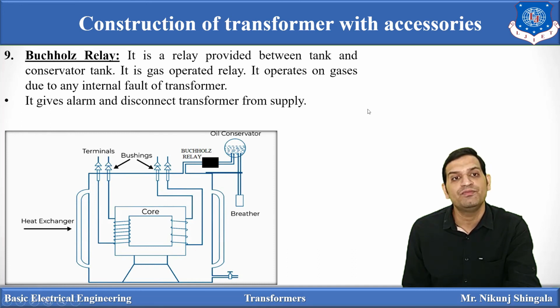So what is the function of that? It gives an alarm to the operator and it can disconnect the transformer from the main supply. If internal faults occur, then the Buchholz relay will operate and the transformer can be disconnected from the main supply so that further damage to the transformer can be prevented. Basically, the Buchholz relay is used to provide protection to the transformer under any fault condition.